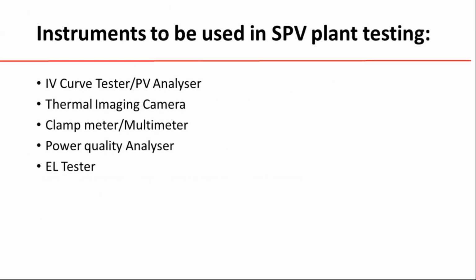These are a few instruments used in solar photovoltaic power plant testing: IV curve tester, also called PV analyzer, and thermal imaging cameras. This is also a very advanced tool used for hotspot detection on solar panels at the temperature level. Then clamp meter up to 1000 volt and 1500 volt, and the same applies for multimeter also.